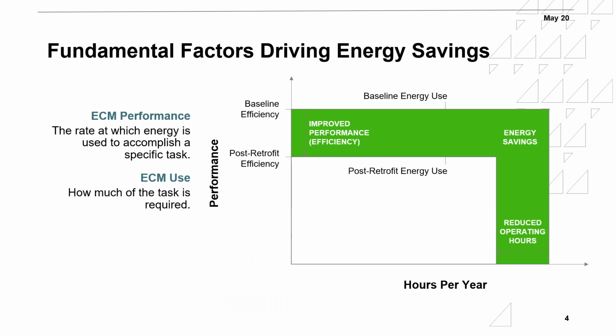Now, when we look at fundamental factors driving energy savings, 2 weeks ago, maybe 10 days ago, we did a presentation on energy audits. Basically, if you want to reduce energy use in a system, in a building, you can look at two things. One is to increase the performance, or get a better efficiency, on a specific piece of equipment. The second is reducing the operating hours. As we know, energy is equal to kW times hours. I can either reduce kW and get a reduction in energy consumption, or I can reduce the hours of consumption, or I can reduce both.